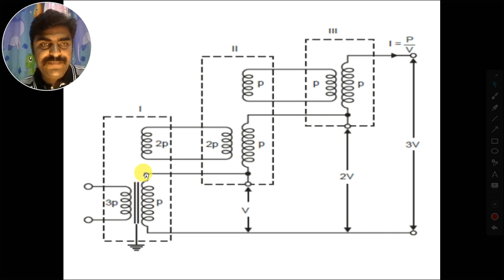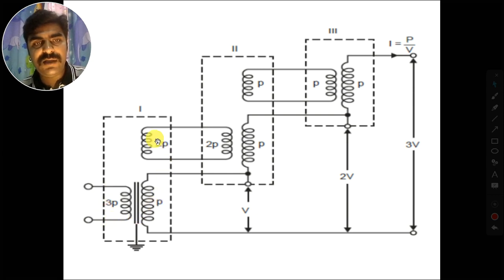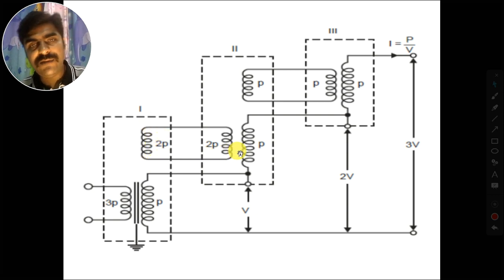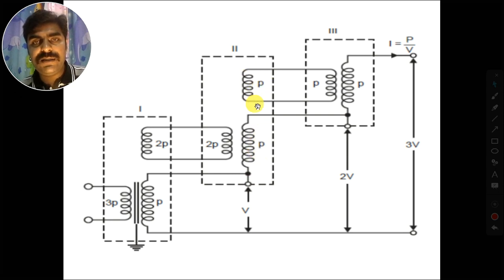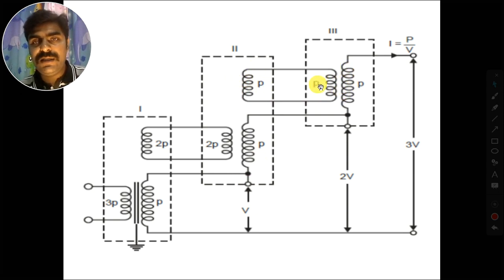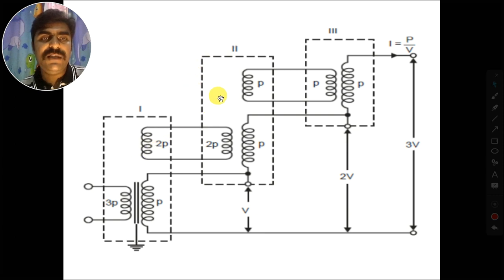Another important point is that the first stage transformer has three windings: primary, secondary, and tertiary or auxiliary winding. The output of this auxiliary winding is given as input to the second stage transformer. The second stage transformer also has a tertiary or auxiliary winding, and the output of that auxiliary winding is given as input to the third stage transformer. Only the third stage is a two-winding transformer; the first and second stage transformers are three-winding transformers.